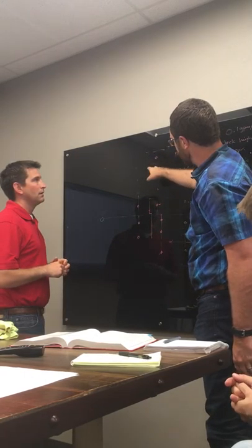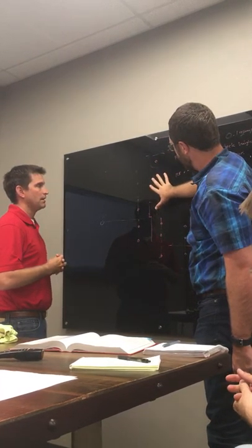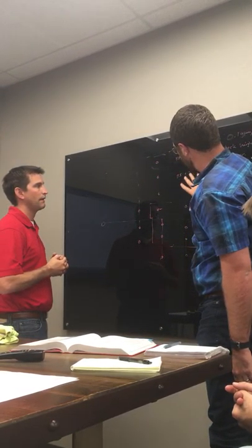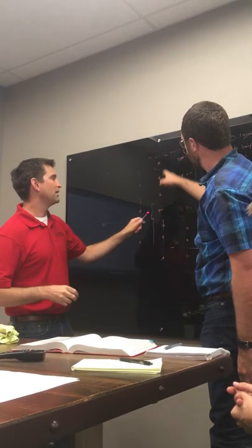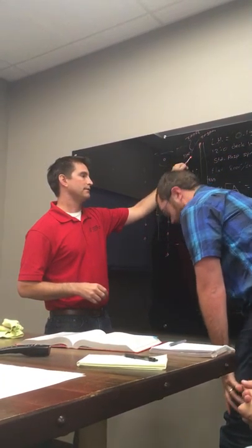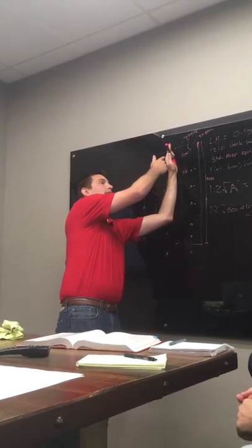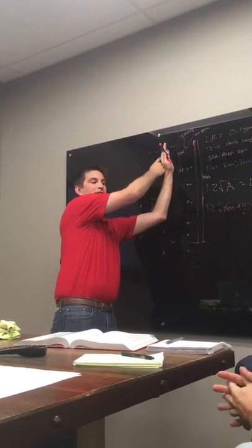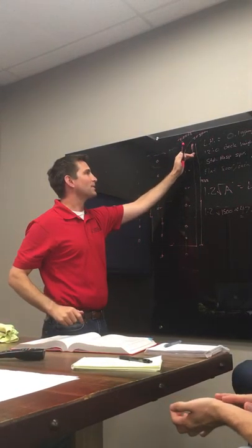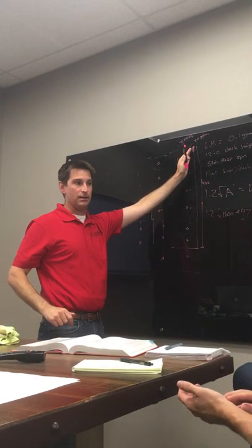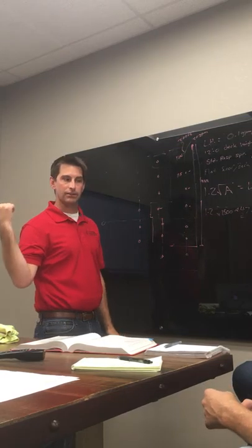Like if you said that's the end of your remote area, none of these are flowing, so they're not in a situation where these are pulling more. But they're all being driven by this head. If you didn't take that out and you started your remote area at this head, then that one's going to be most demanding because it's a starting head. But because this one's driving the calc, it's further away. And I can show you on AutoSPRINK.